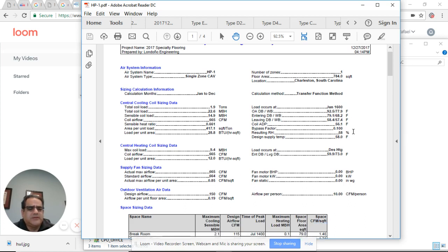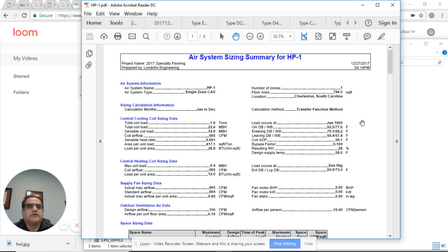There are, of course, times that it gets even hotter than that, but the calculations are done for, I think, cases that only happen 97% of the time. So there's a number there that we're required to follow. Of course, sometimes it feels like 100 degrees, so we just can't go and punch in 100 degrees, because air conditioning isn't sized for the super worst day of the year. It's worse for 97% of the time, or whatever that number is. So that's where that comes from.